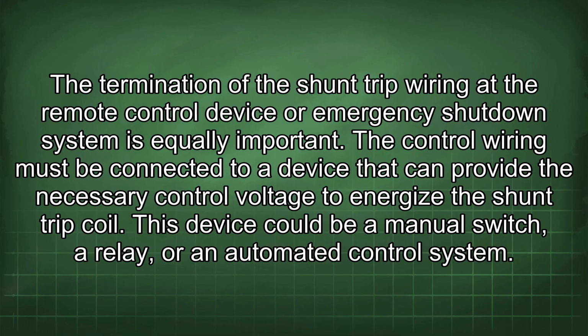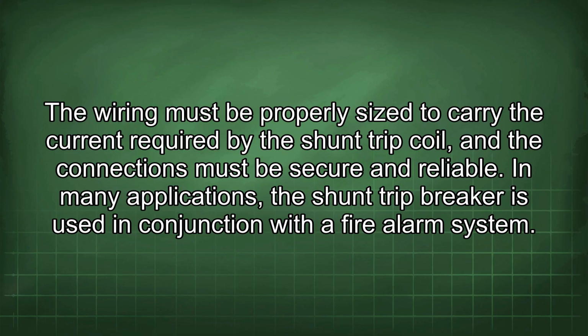The termination of the shunt trip wiring at the remote control device or emergency shutdown system is equally important. The control wiring must be connected to a device that can provide the necessary control voltage to energize the shunt trip coil. This device could be a manual switch, a relay, or an automated control system. The wiring must be properly sized to carry the current required by the shunt trip coil, and the connections must be secure and reliable. In many applications, the shunt trip breaker is used in conjunction with a fire alarm system.